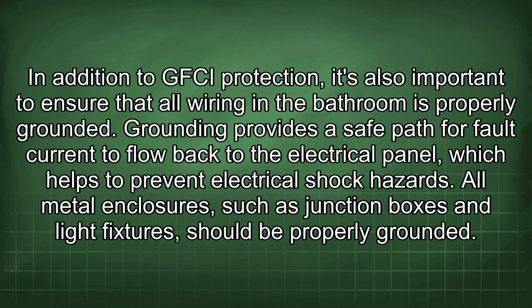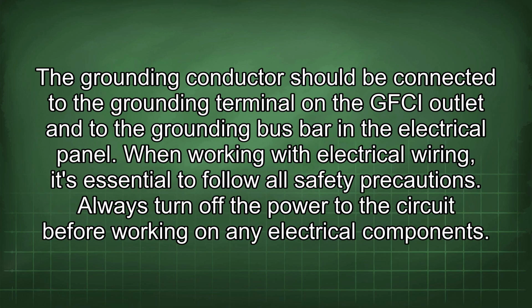In addition to GFCI protection, it's also important to ensure that all wiring in the bathroom is properly grounded. Grounding provides a safe path for fault current to flow back to the electrical panel, which helps to prevent electrical shock hazards. All metal enclosures, such as junction boxes and light fixtures, should be properly grounded. The grounding conductor should be connected to the grounding terminal on the GFCI outlet and to the grounding bus bar in the electrical panel.